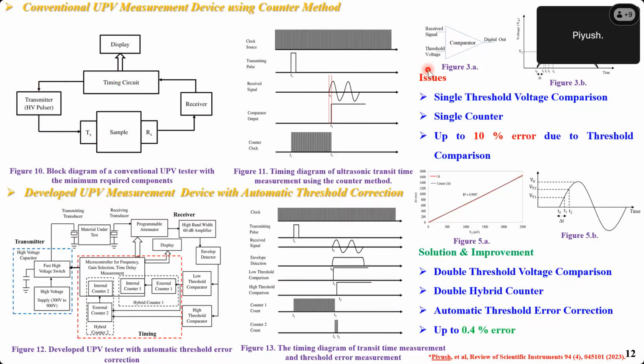To stop any timer, we require a digital signal, and that digital signal we can get from a comparator. So we have to compare our analog signal with a threshold voltage. Here you can see that ideally we have to stop our counter at T0. But due to the threshold voltage Vt, it stops at T1, which produces an error from T1 to T0. And it varies with the gain. Gain depends on the amplitude of the receiving signal. So these are the issues in the present instrument which produce 10% error in the measurement, which is very huge.